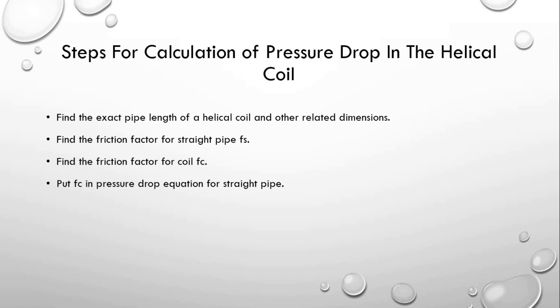In the second step, we find the friction factor for the straight pipe. I will not discuss the determination of the friction factor here; it is assumed that people know how to determine it for a straight pipe. Then, using various correlations given below, we find the friction factor for the helical coil. At the end, this friction factor is inserted into the equation used for straight pipe pressure drop calculation, and this equation then gives the pressure drop in the helical coil, because we are using the friction factor for the coil, not for the straight pipe.